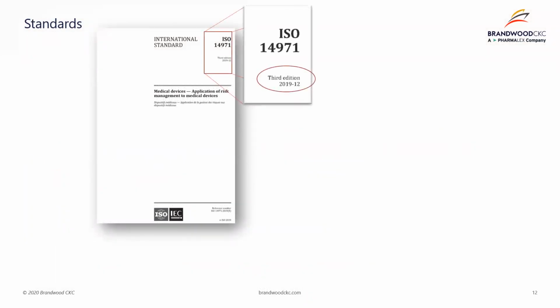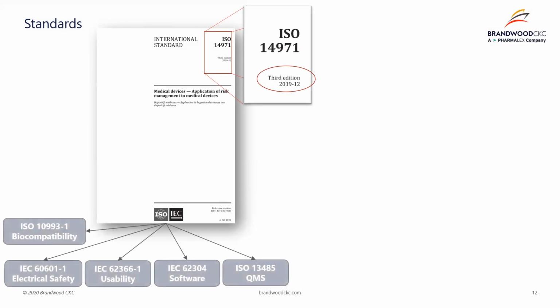The current edition of the ISO 14971 standard is 2019. There were a number of changes from the 2007 edition, which we'll cover in the next slide. This standard is referenced in most medical device safety standards, such as IEC 60601-1, IEC 62304, IEC 62366-1, ISO 10993-1. These standards can be used to mitigate known risks. Also, ISO 13485 references the standard for inclusion in the manufacturer's quality management system processes.